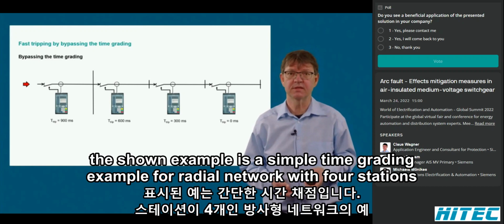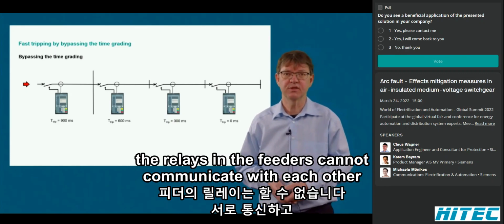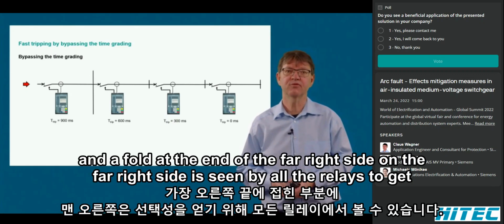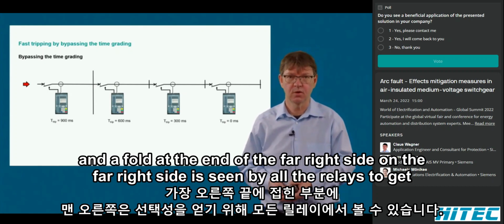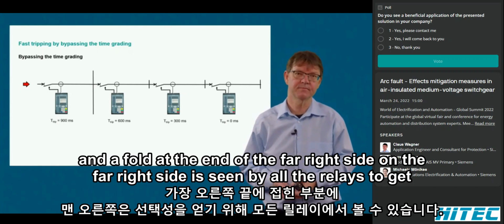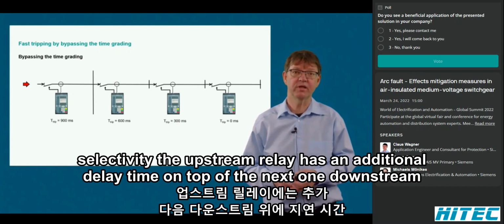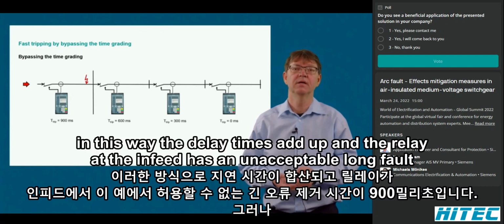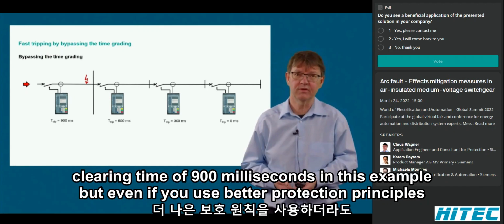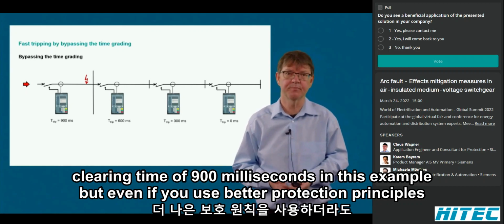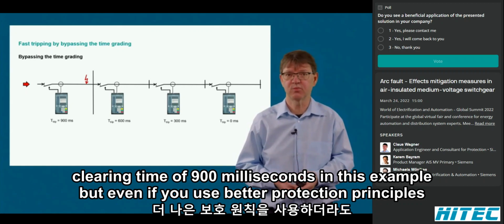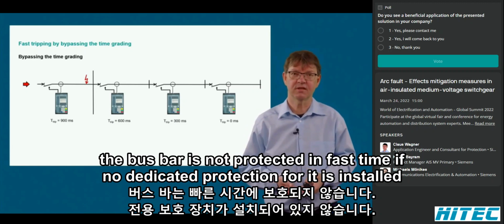The shown example is a simple time grading example for a radial network with 4 stations. The relays in the feeders cannot communicate with each other, and the fault on the far right side is seen by all the relays. To get selectivity, the upstream relay has an additional delay time on top of the next one downstream. In this way, the delay times add up, and the relay at the in-feed has an unacceptable long fault clearing time of 900 milliseconds in this example. But even if you use better protection principles, the busbar is not protected in fast time if no dedicated protection for it is installed.